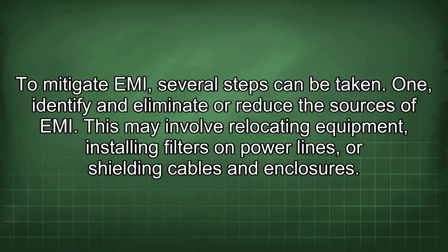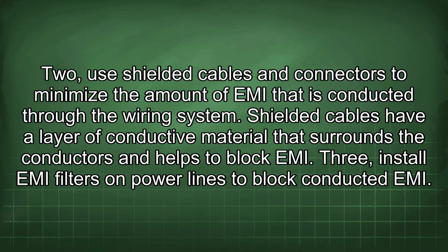To mitigate EMI, several steps can be taken. 1. Identify and eliminate or reduce the sources of EMI. This may involve relocating equipment, installing filters on power lines, or shielding cables and enclosures. 2. Use shielded cables and connectors to minimize the amount of EMI that is conducted through the wiring system. Shielded cables have a layer of conductive material that surrounds the conductors and helps to block EMI.